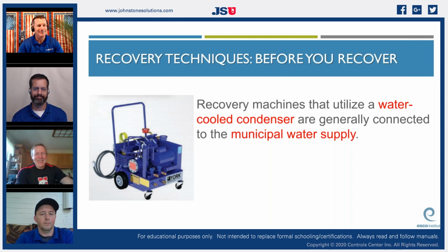Recovery machines that utilize a water-cooled condenser must be hooked up to water. Yeah, you've got to have a water source for them. But this is probably for very large recovery systems, like Clifton's talking about recovering 1,200, 1,400 pounds. I mean, we know how difficult it is as service techs just to recover 8 pounds sometimes from a system.